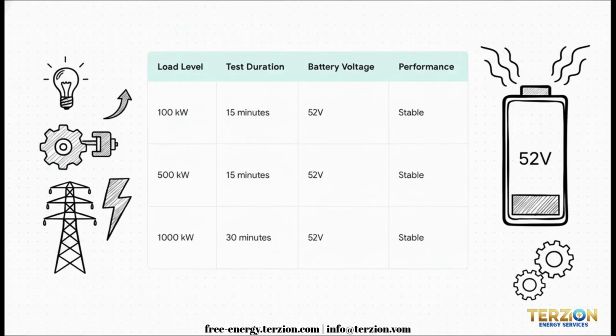During the official tests, the load was cranked up, step by step, from 100 kilowatts all the way up to a full megawatt. And as you can see from the data, at every single stage, the starting battery's voltage held perfectly stable at 52 volts.